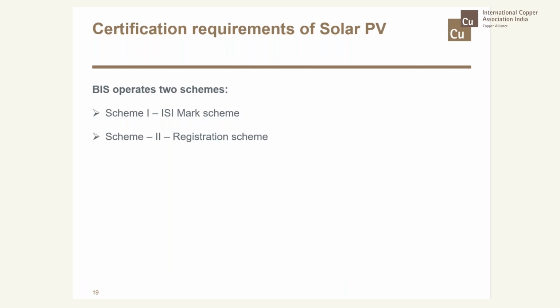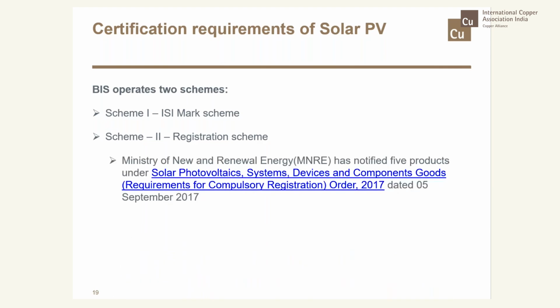The certification requirement of solar PV is operated in India by BIS. There are two schemes in operation. Scheme 1 is the normal ISI mark scheme, which many of you are familiar with. Many product standards are also covered under mandatory ISI mark certification, like cables, MCB, fuses, etc., which are also used in solar PV. For solar PV, another type of certification scheme, scheme 2, is used, for which a different symbol is used. This symbol you can find on laptops, TVs, many other electronic goods, LED lighting, and now in solar PV. It is based on a type test certificate issued by a BIS recognized laboratory, and certification is issued based on documents submitted, and no factory visit is required. It is much simpler than the ISI mark scheme. Details are of course available on the BIS website. This is what I said, that the Ministry of MNRE has made it mandatory.